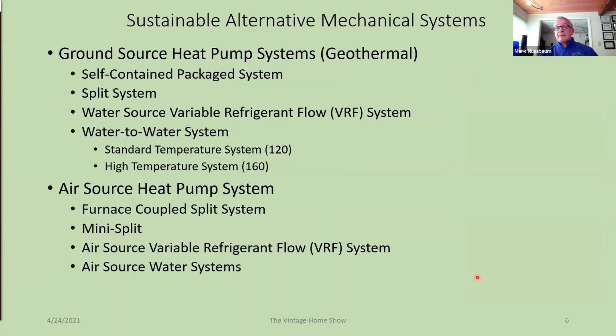Looking at some of the sustainable options that we have, I'm going to focus today, just for time, on ground source heat pump systems and air source heat pump systems. This covers the bulk of the higher efficiency options. So on the ground source side, you've got a self-contained or a package system, which is just one box inside that does everything. You can do a split system, and the rest of these items are all kind of the same for both air source and ground source.